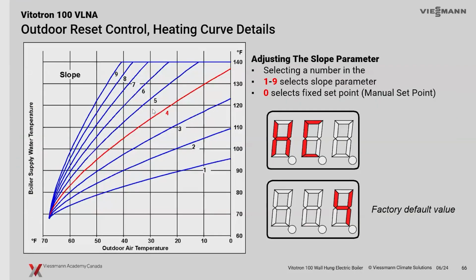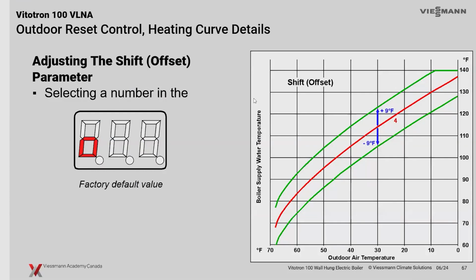So I can't really tell you where those numbers are going to be. It's all based on your heating system and what your requirements are, but you get some ideas of the max temperatures that we're looking at here. So again, this is all in Fahrenheit. We're down to 0 degrees Fahrenheit here on our scale, and of course, riding up to a maximum temperature of 140 Fahrenheit on that system. And of course, there's our shift and now our slope.